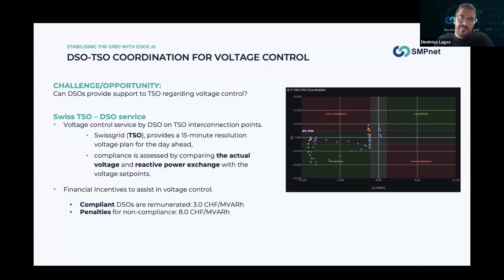So if we have an incident of overvoltage and the distribution system is absorbing reactive power, then it is compliant. It is in the green region that we see here because it helps the voltage control of the transmission system. If it is an overvoltage situation, then it should absorb reactive power to support the transmission system. If it does the opposite, for example, injecting reactive power when we have overvoltage, then it falls in the non-compliant region.